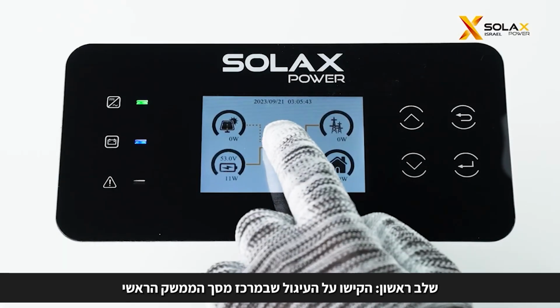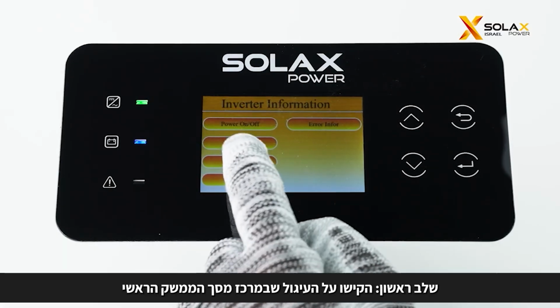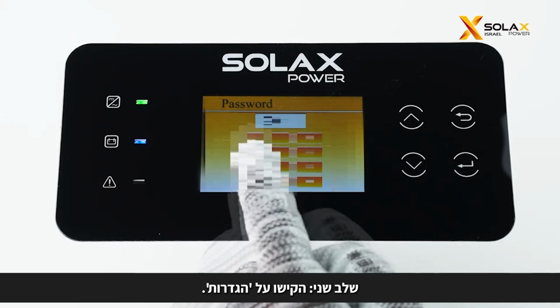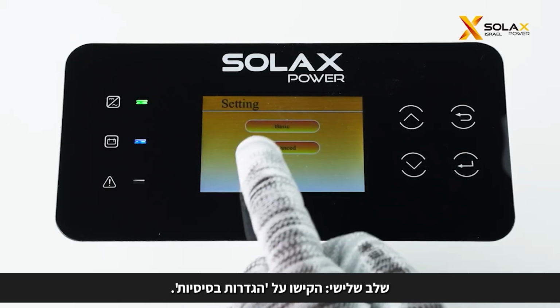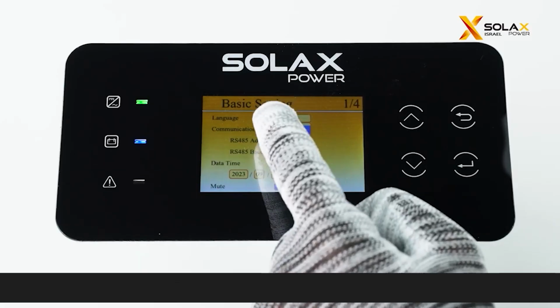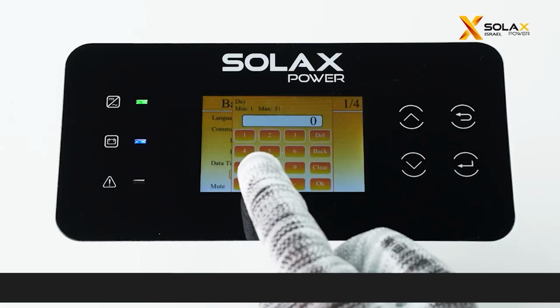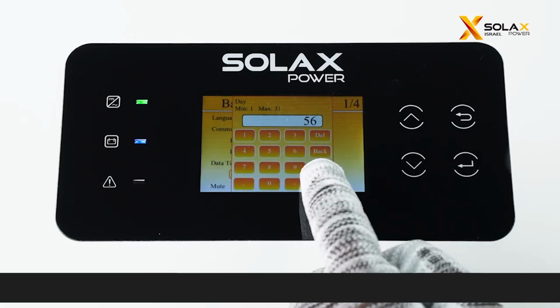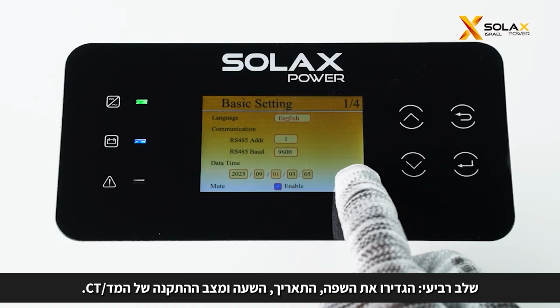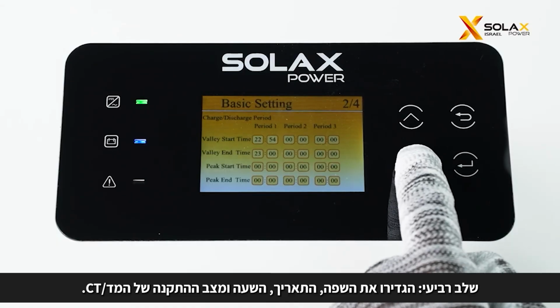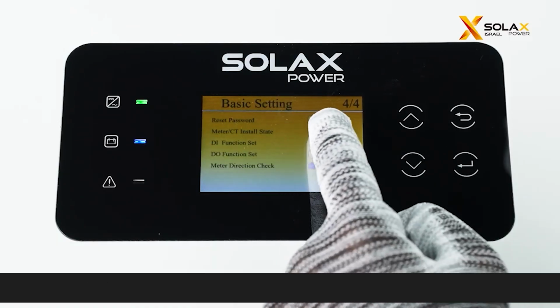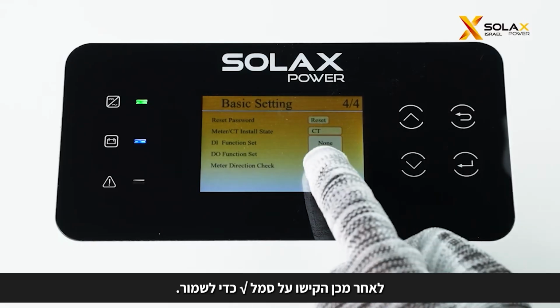Step 1. Tap the circle in the middle of the main interface screen to enter the main menu. Step 2. Tap Setting. Step 3. Tap Basic Setting. Step 4. Set the language, date, time, and meter/CT install state. Then tap the check mark to save.